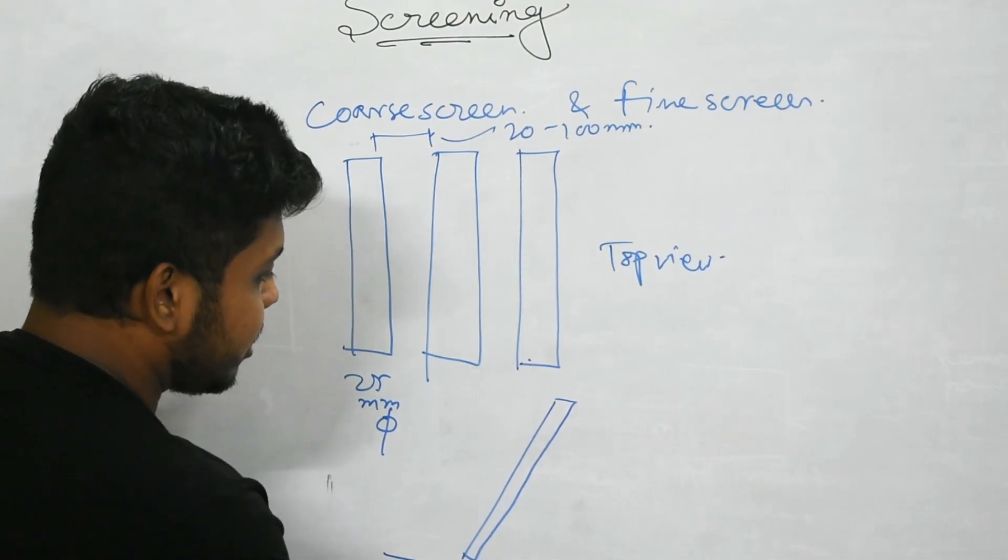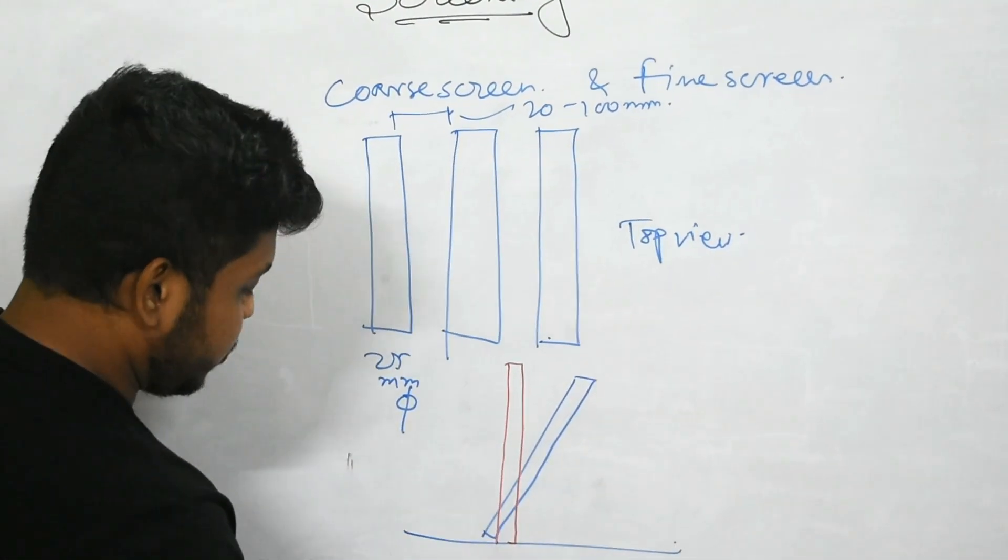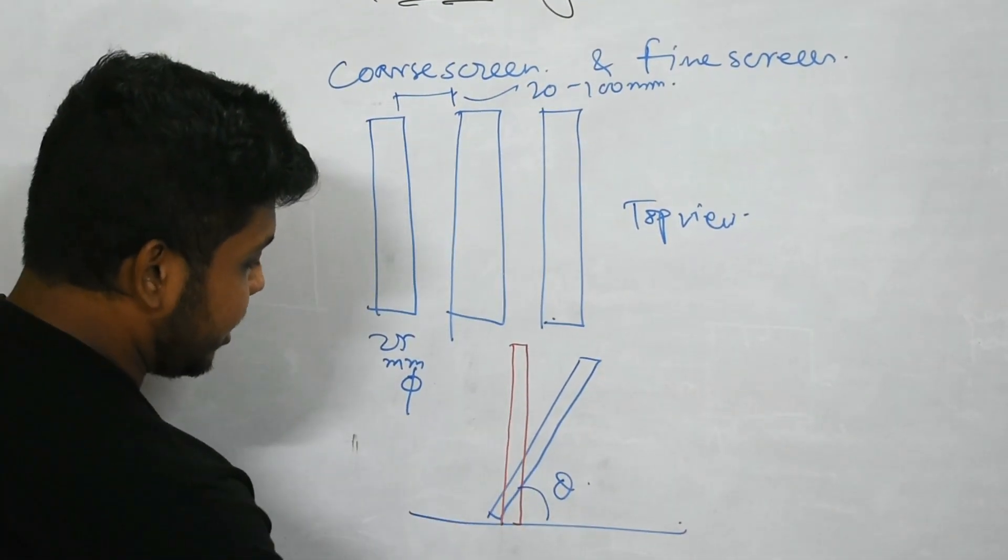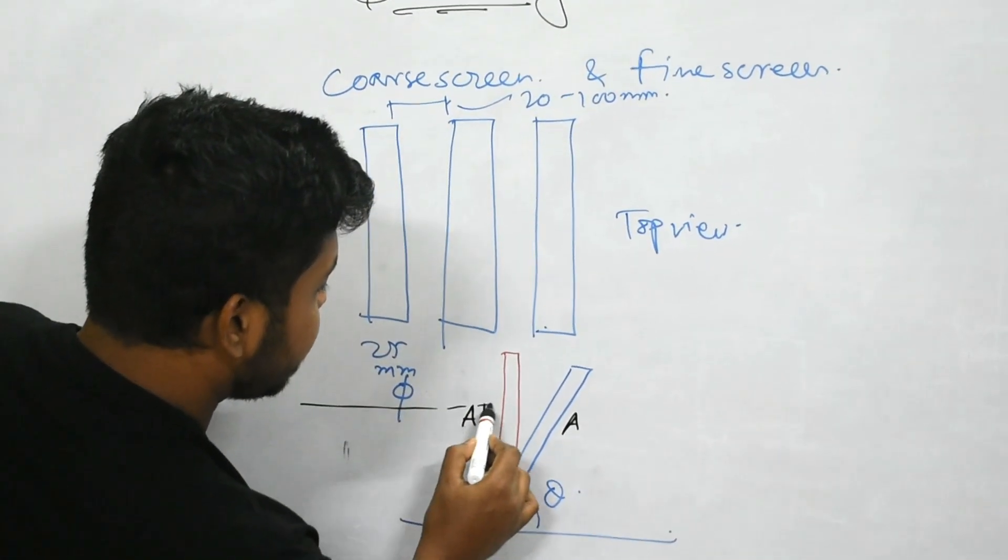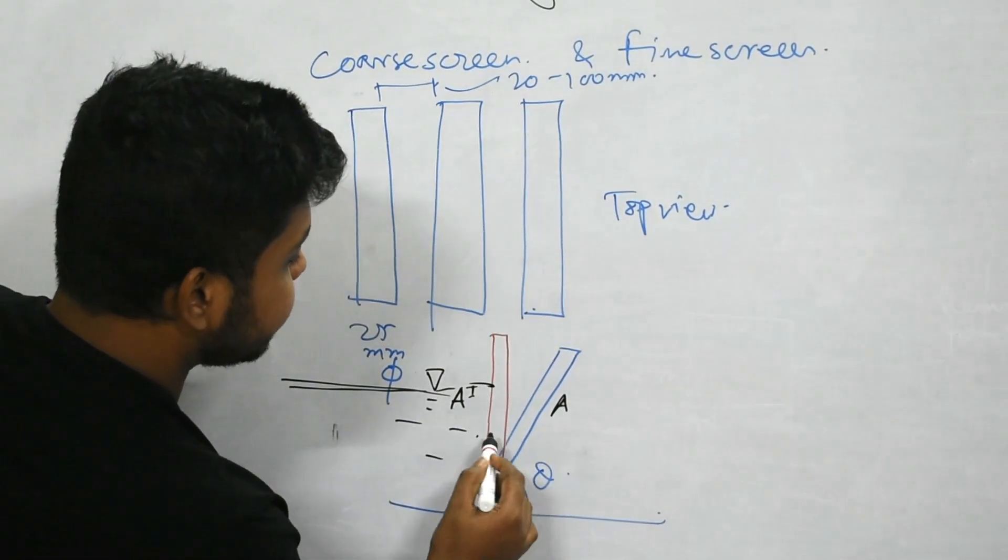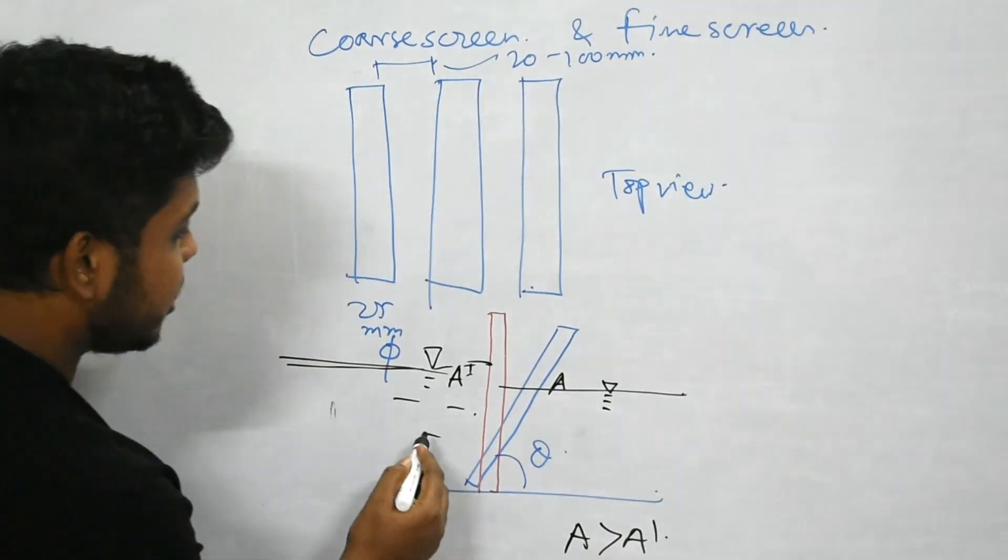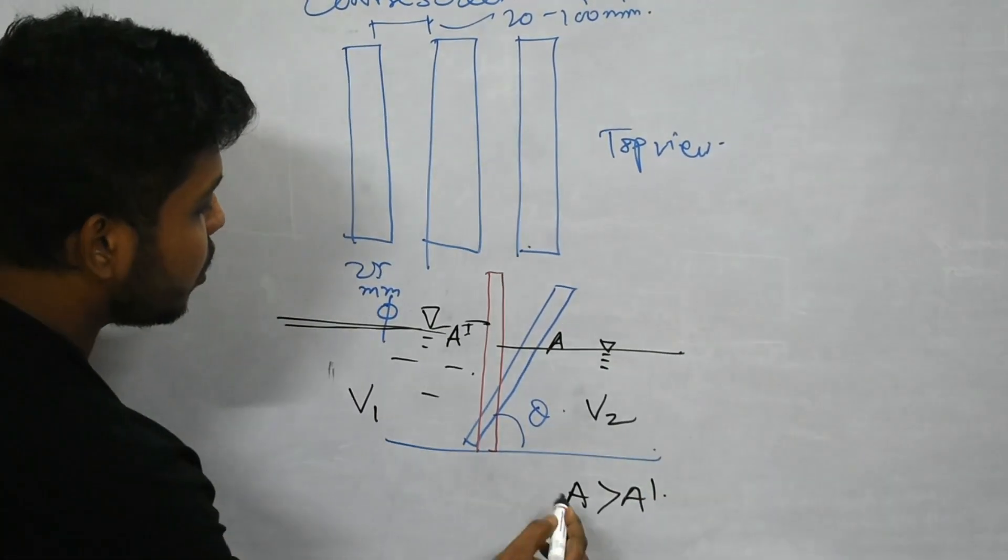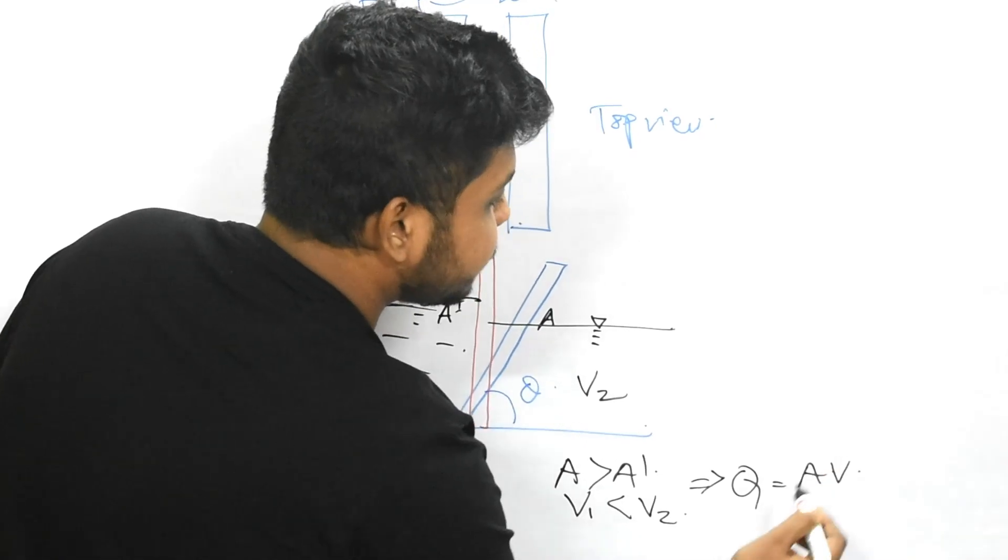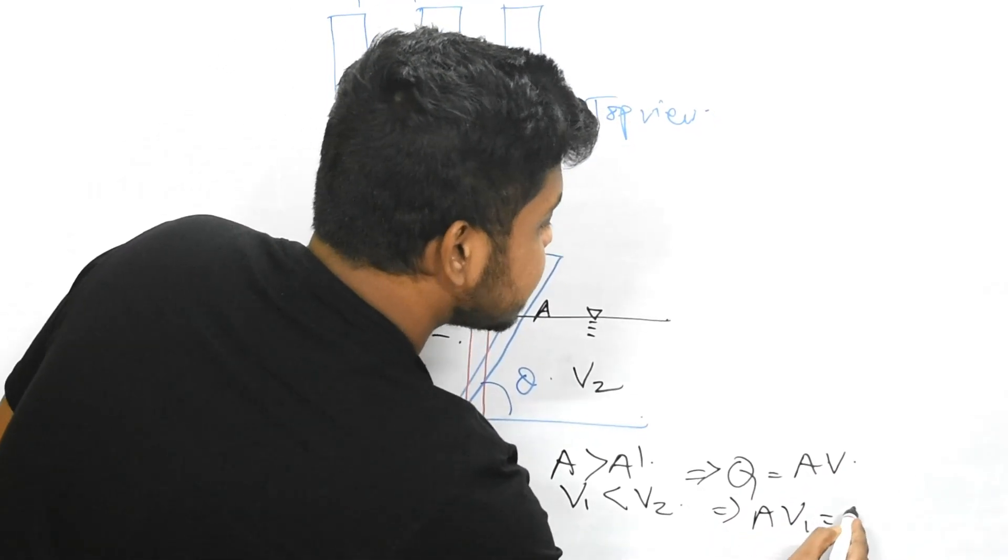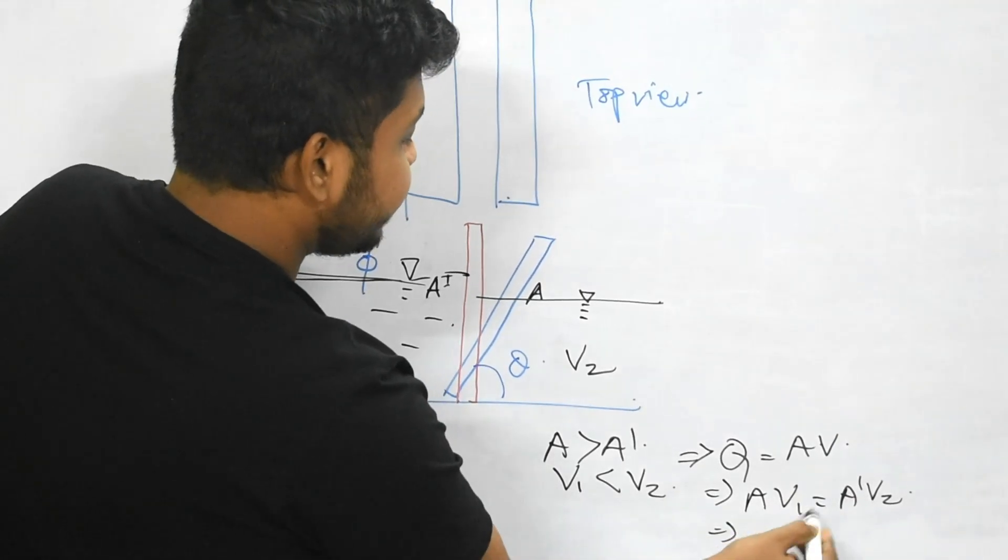We will check if these bars are provided in some vertical alignment versus at an angle theta. If this area is A' and this new area is A, the water coming from this side will have different velocities. A will be more than A'. If this velocity here is v1 and here velocity is v2, then v1 will be less than v2 as Q equals A into v. To maintain this, A into v1 equals A' into v2. As A is greater than A' to maintain the flow, v1 will be less than v2.